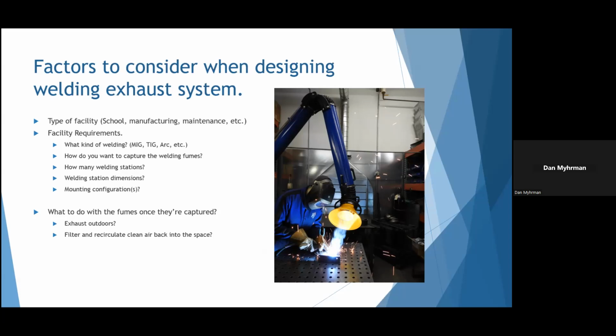Once everything's captured, once the fumes are into ductwork and make their way through the fan, you want to figure out what to do with them. You basically have two options: exhaust it outside, or you can filter it and recirculate it back into the space. I typically recommend filtering and returning it back to the space in larger systems so you don't have to worry about makeup air.